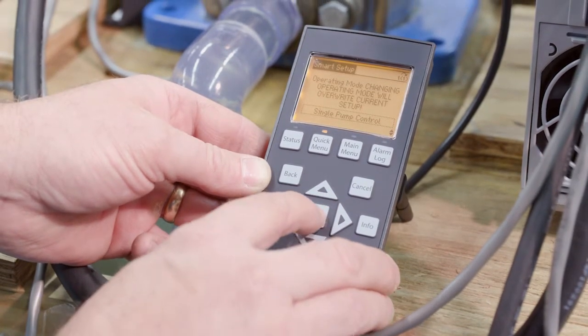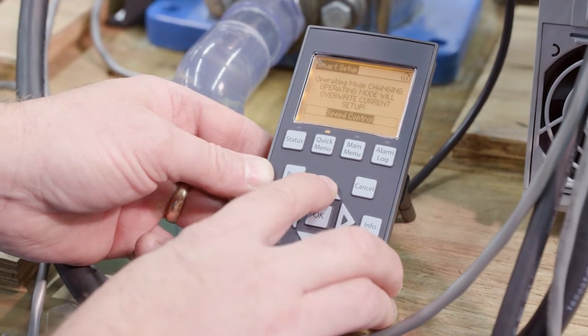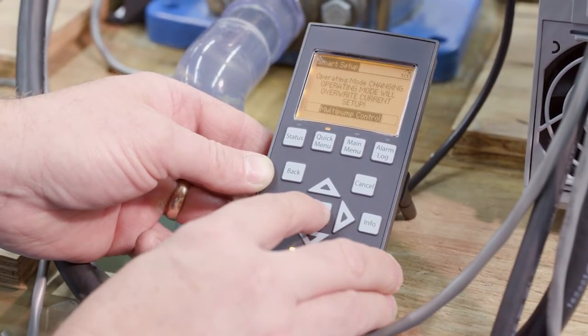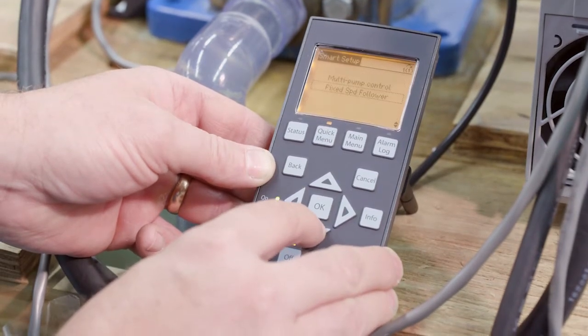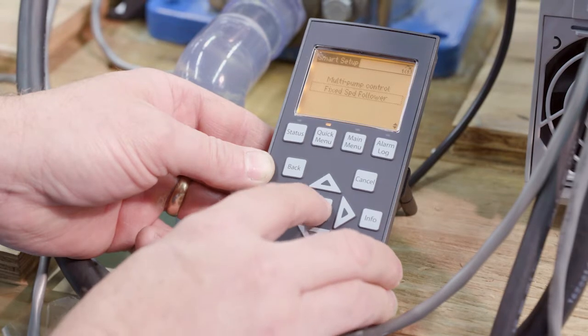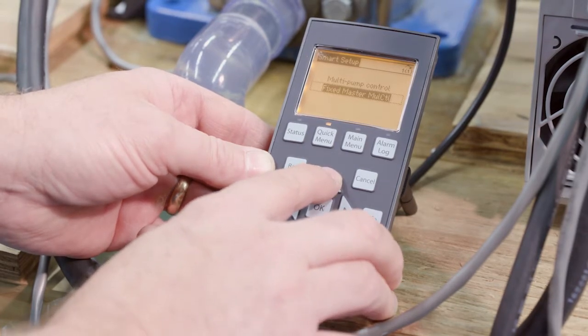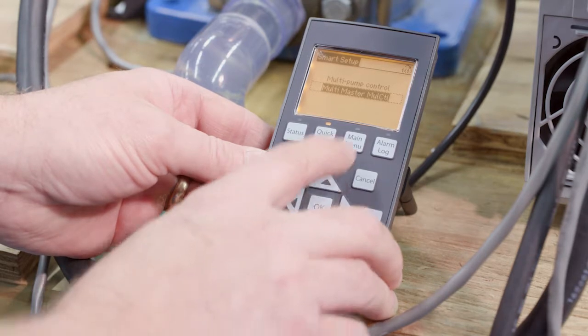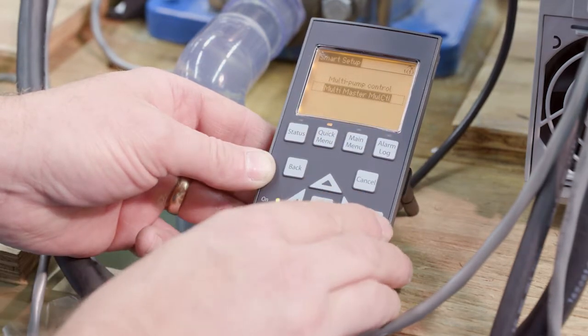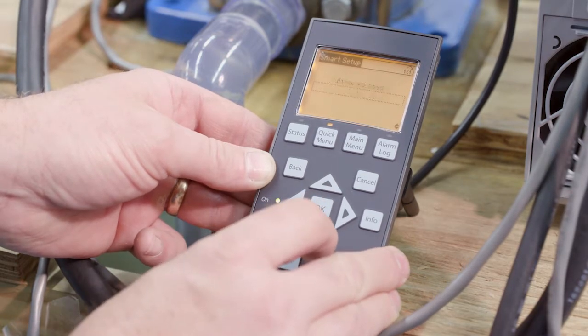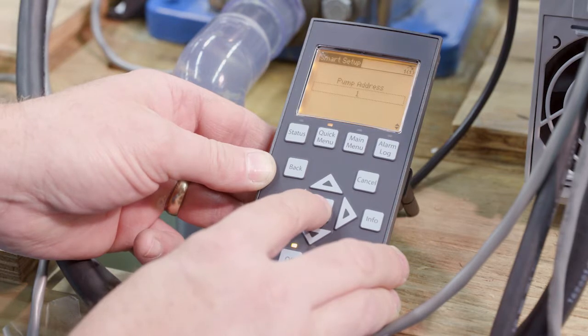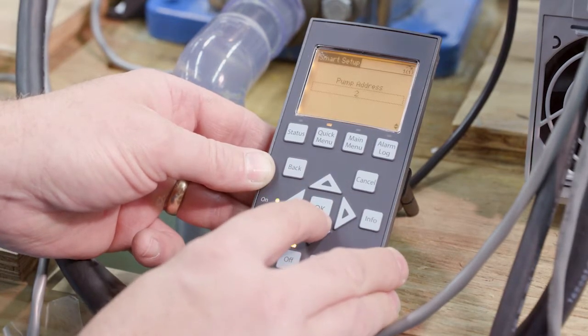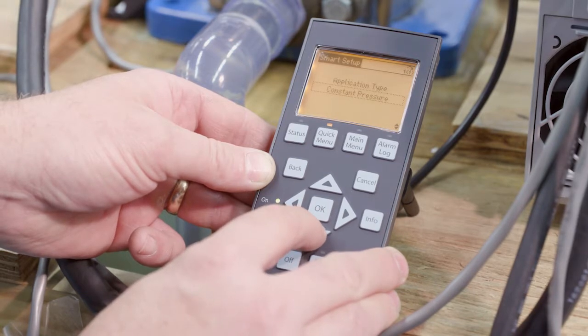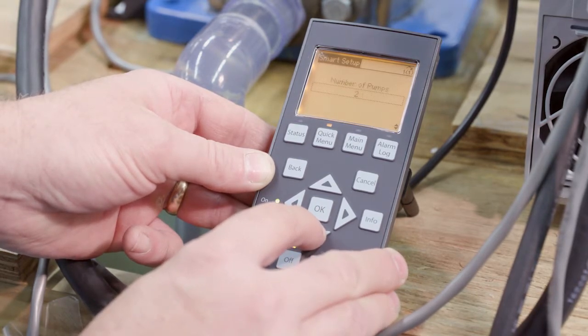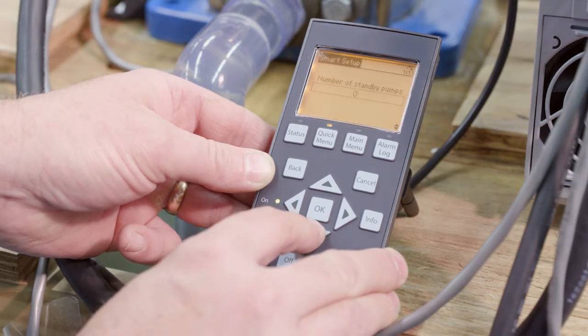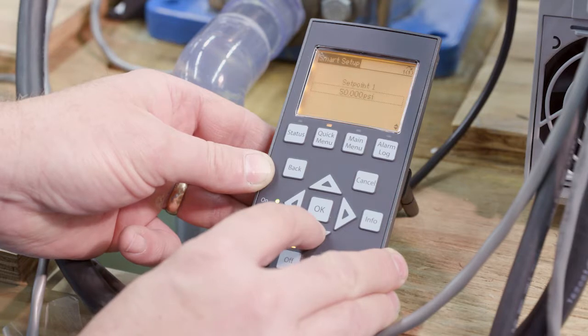And again, default is single, right? So we want multi-pump control. We've got a duplex. Now it's saying what type of multi-pump control do you want? So we want to match that to multi-master, multi-control, same as the lead. You want to make sure you save it. Pump address, right? So very important, I have to change this address. Lead was 1, lag is going to be 2. Constant pressure, number of pumps 2, standby 0. Auto set, yeah, we'll do an auto set.